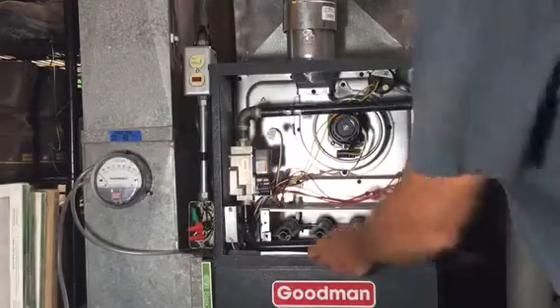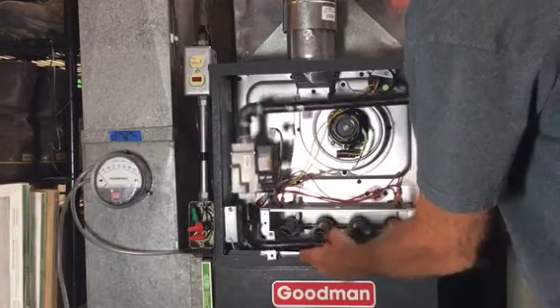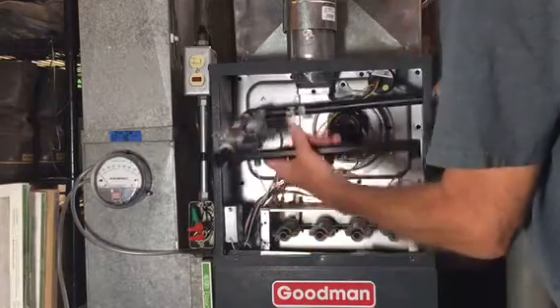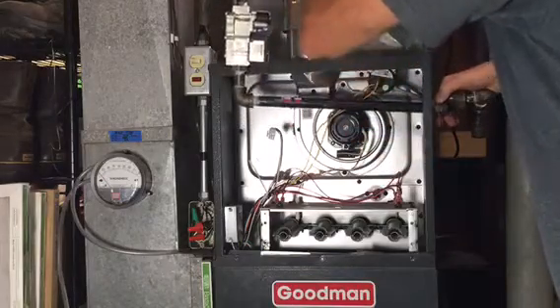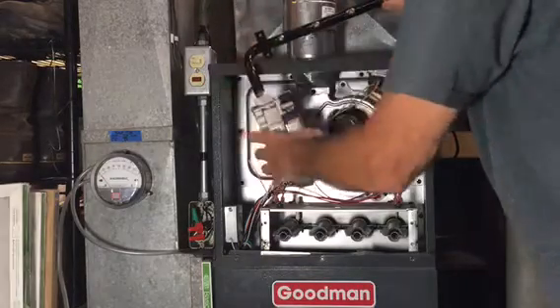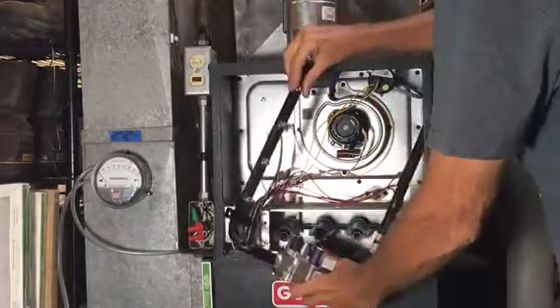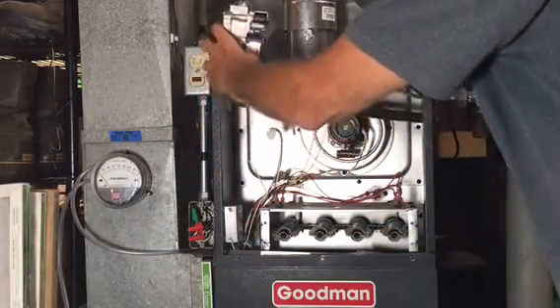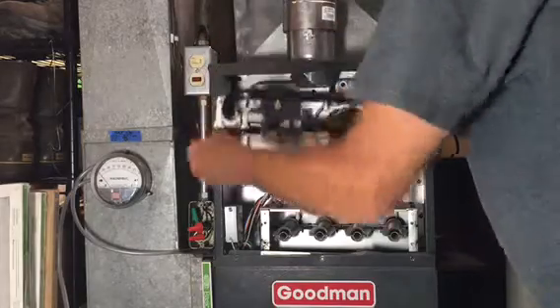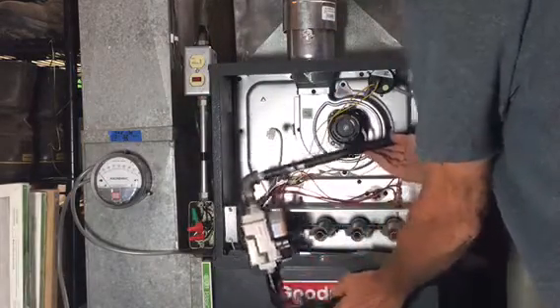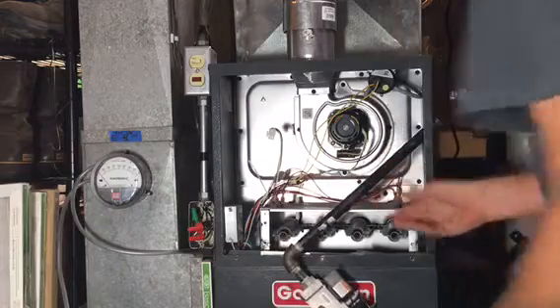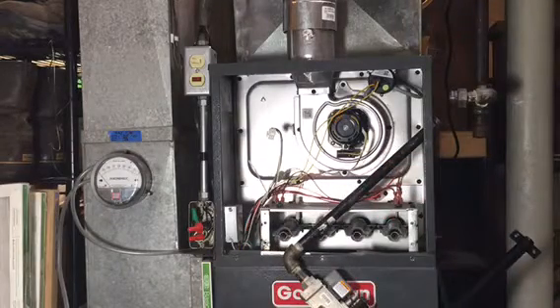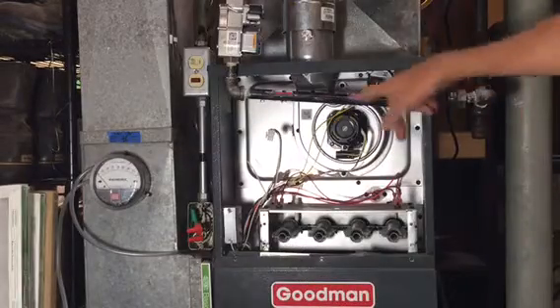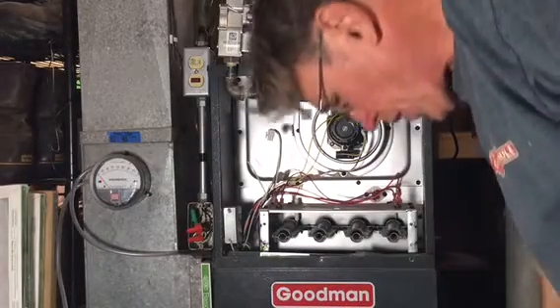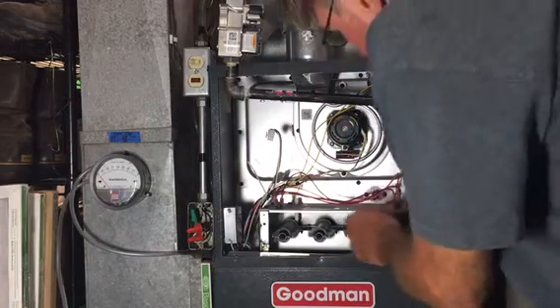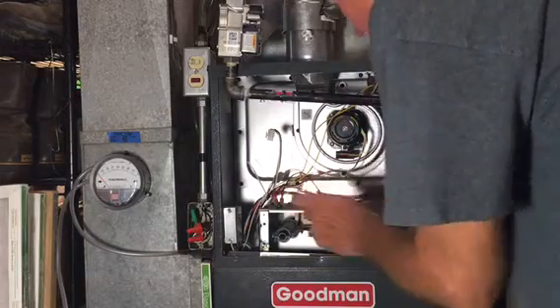Okay, now we've got the 4 bolts out here, and you'll see with the gas line disconnected, I can rotate the gas valve out of the way. I don't think I can get it out. We'll just get some wire, tie it up, just so it's out of the way here. Okay, now we've got the manifold tied up here to the piece of conduit to get it out of the way. We have to take out the burner assembly, and that's not difficult. There's just another 4 screws.